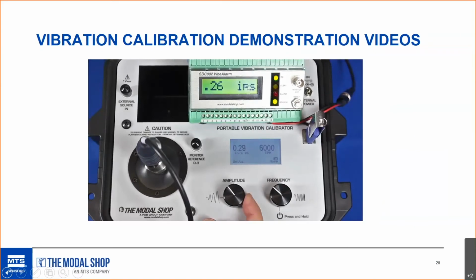The first alert is going to occur at a half inch per second peak. As soon as I creep over that number on the calibrator and the vibe alarm catches up, we have a 3-second time delay, and boom, you see the alert light trigger. Now we'll do the same thing for the vibration shutdown alarm, which is at 1 inch per second. The portable calibrator output is again in blue. Once the vibe alarm catches up, we have the 3-second time delay, and you see the alarm trigger. In a nutshell, that's the primary application for the portable vibration calibrator.